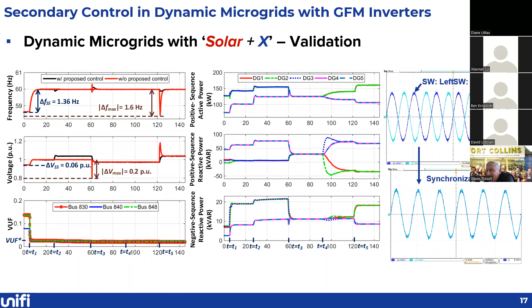For example, when we are about to close the switch, we need to activate a corresponding compensation term in the system to synchronize the system - basically to synchronize the voltage across the switches using our power electronics inverters. After the synchronization, the difference between the two waveforms can be significantly minimized. So that is the way for us to mitigate the impacts during the transients.